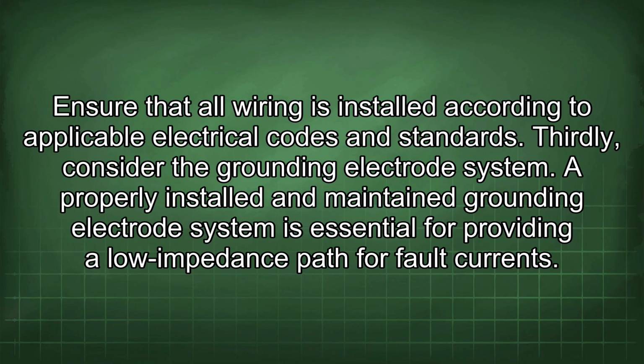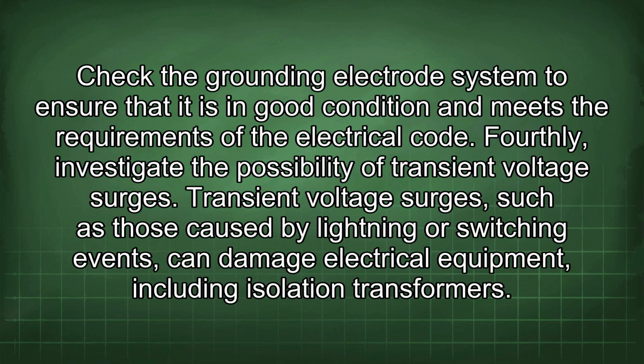Thirdly, consider the grounding electrode system. A properly installed and maintained grounding electrode system is essential for providing a low impedance path for fault currents. Check the grounding electrode system to ensure that it is in good condition and meets the requirements of the electrical code. Fourthly, investigate the possibility of transient voltage surges.